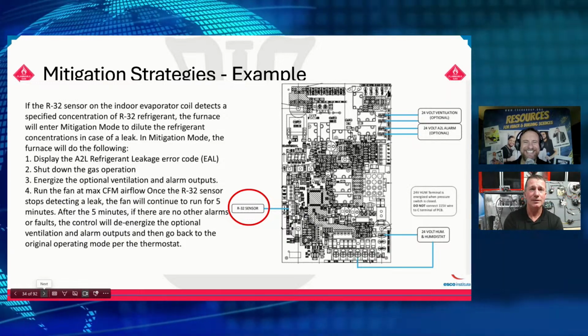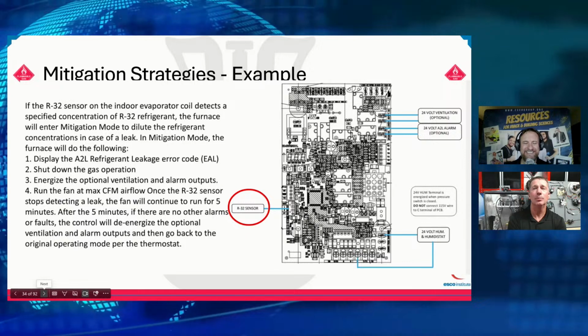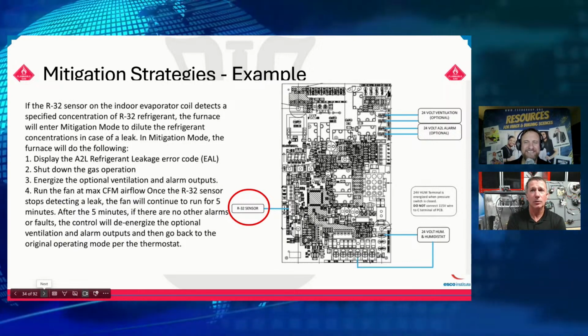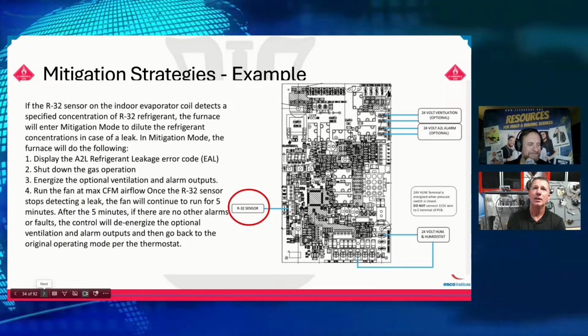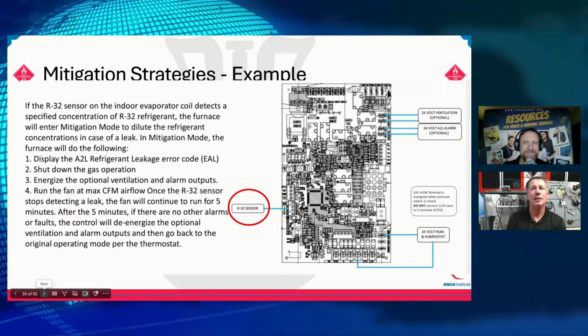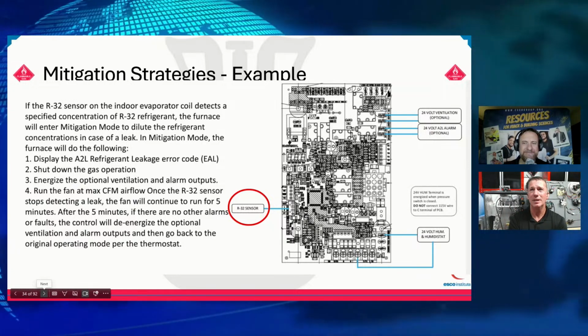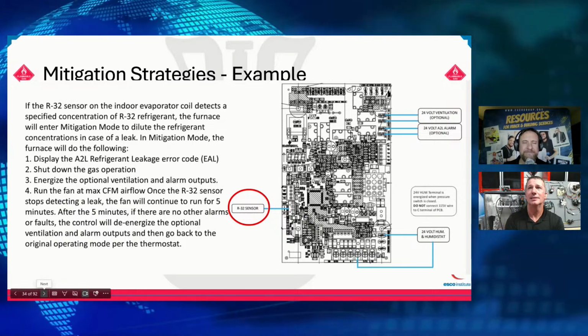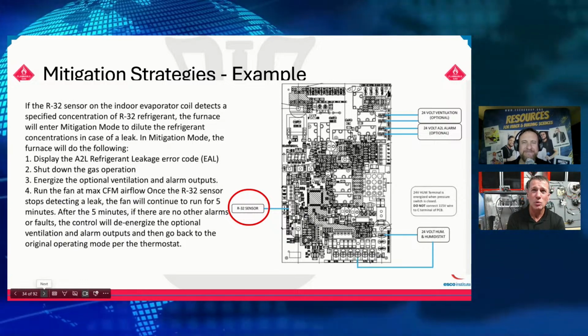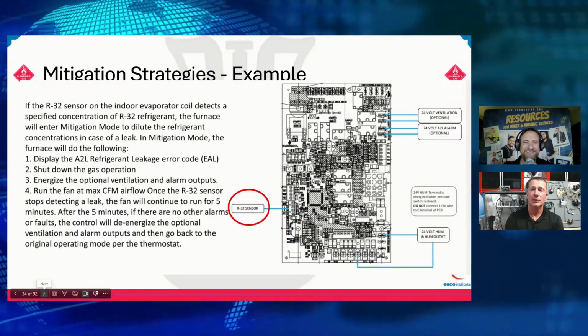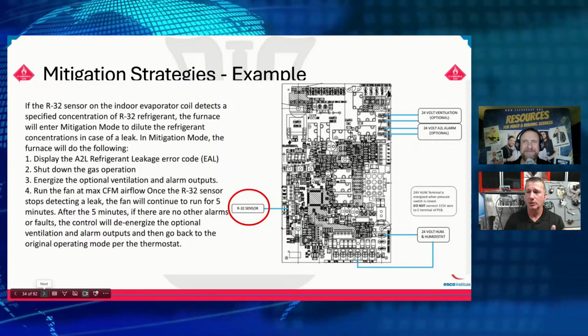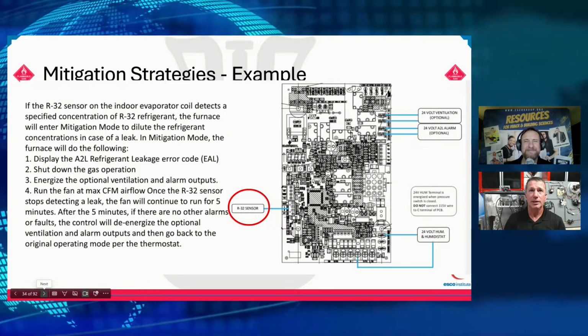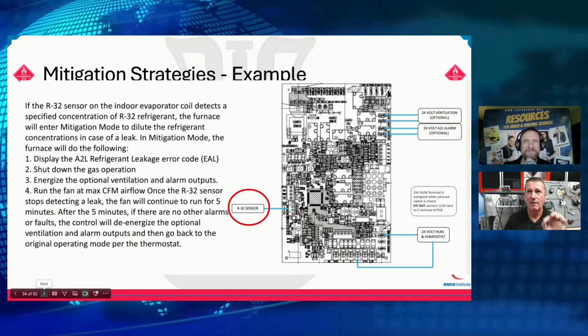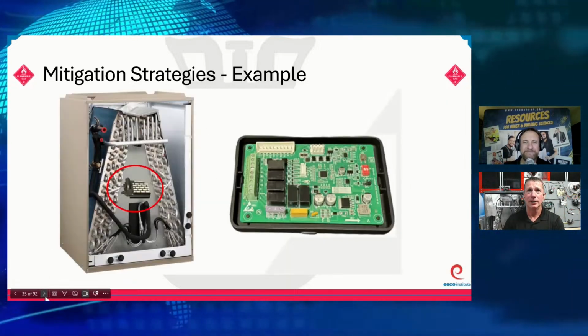So they'd actually received a furnace that had the A2L sensor built into the board, and it was looking for that sensor. I advised him he could go through the menu and find an option for disabling that sensor, for use on an R410-only system. That was our first opportunity to see a board with the sensor built onto the factory board, and that was over a year ago.